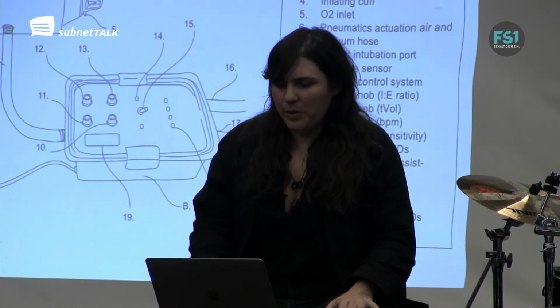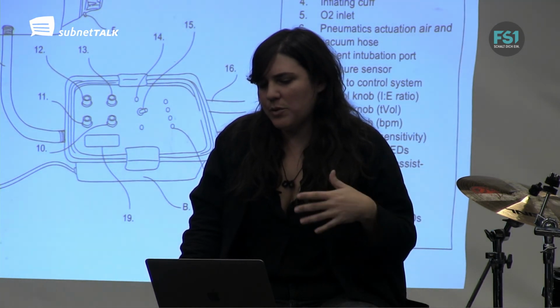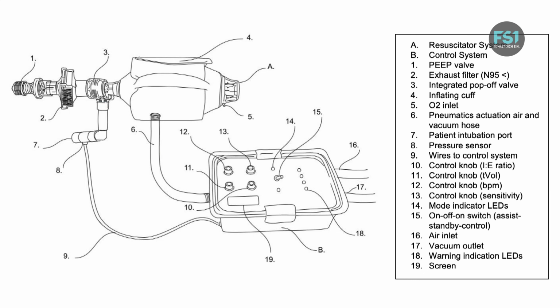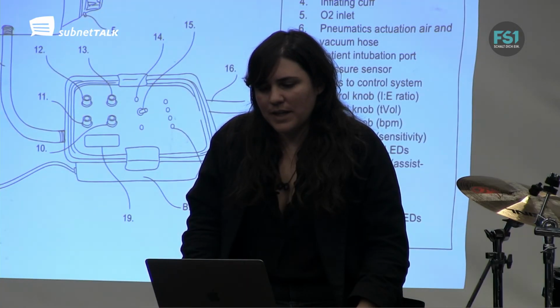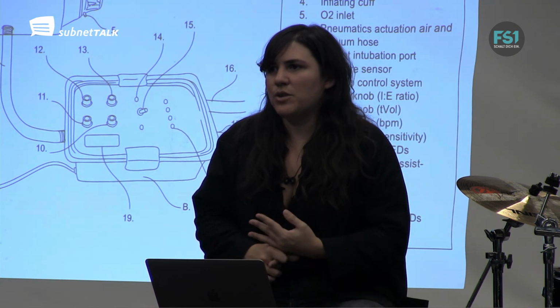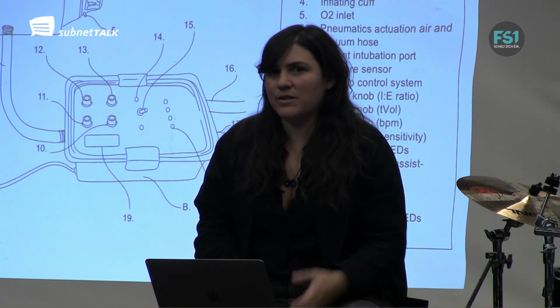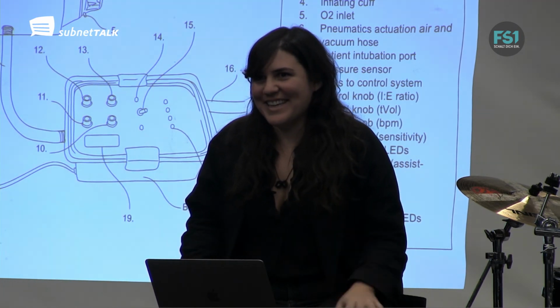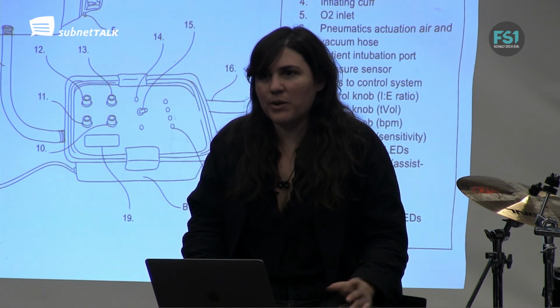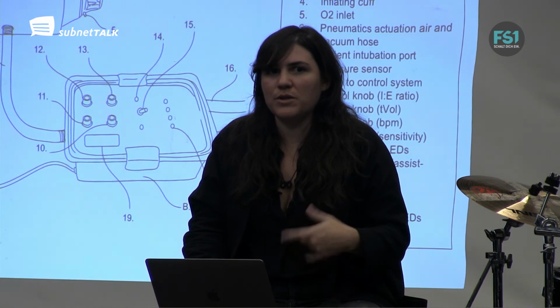Here's a drawing of all the components that it has. Usually ambu bags are just manual, and they come with a PEEP valve, so you can set the pressure that you need to add to the patient, and you can also have a pop-off valve, so in case you pressurize the patient too much, it'll just open up and you won't blow up their lungs, which is important. Then an N95 filter, which is also very customary. It has a knob for the IE ratio, inspiration to expiration, which is actually really important. You'd think, whatever, they'll breathe, but leaving time for expiration is extremely important because you will not be able to get rid of your CO2 if you don't exhale.